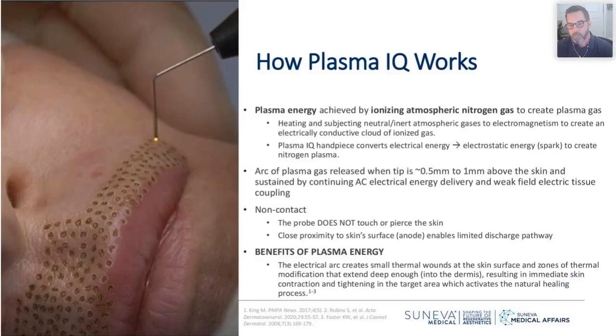What's also interesting about this particular technology is you're not applying the tip or the electrode directly to the skin. It's about 1 millimeter away from the skin. There's an energy arc that goes across it, and you can kind of see it here. If you can see my arrow, you can see that light at the tip of the electrode here. That is the plasma energy that's being delivered. So it's non-contact. The probe does not touch the skin. It's in close proximity. When you activate the device, it creates that energy.